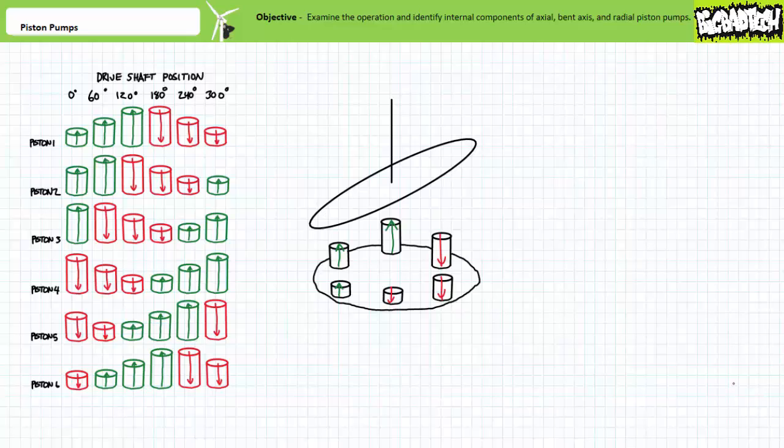When we think of this as a collective of pistons, we have in effect six manual piston pumps all executing the same cycle sequentially offset from each other. As the drive shaft spins the complete assembly — the swash plate, pistons, and piston block — piston after piston follows in succession, ensuring at least half the collective is firing while the other half is reloading. An excellent strategy for both smoothing pump pulsations and when confronted by a swarm of zombies.